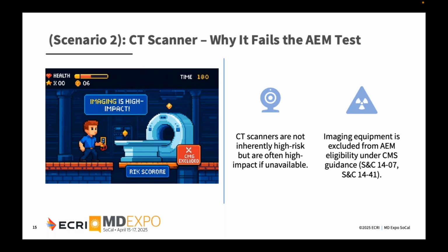Put it in the S&C 1407 and the attached state operating manual from CMS. It states that imaging equipment, imaging slash radiologic, has to have the same frequency and procedures or tasks, whatever the language is, as the original manufacturer equipment. They do go on in that same paragraph to talk about how you can do other devices, right? So I interpret that, and it's been interpreted in this AAMI standard, that if you're compliant with CMS, you can't deviate one way or another. You can't do it even more frequently.